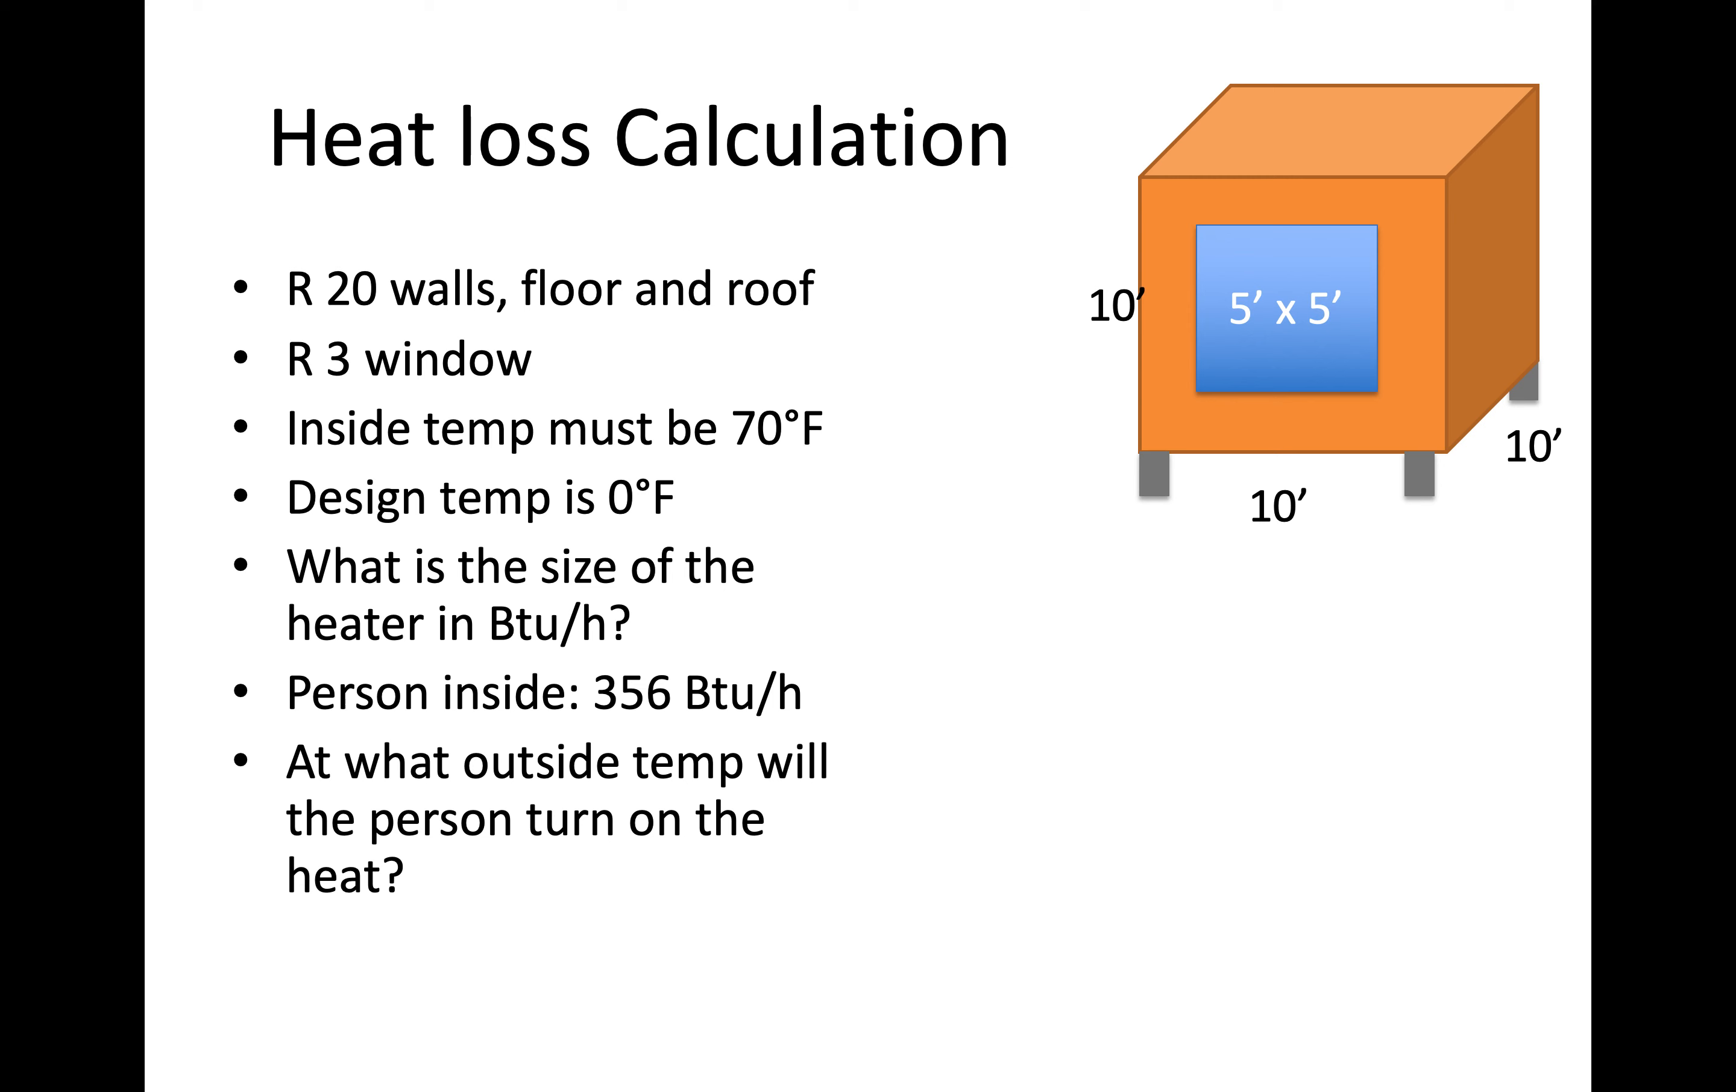So we can use a design temperature, that's a temperature, an outside temperature that is in the 98th percentile worst coldest temperature you're likely to face in this particular location and we can use that information to calculate the size of the heater which we're going to have in BTUs per hour, that's a power of a heater.